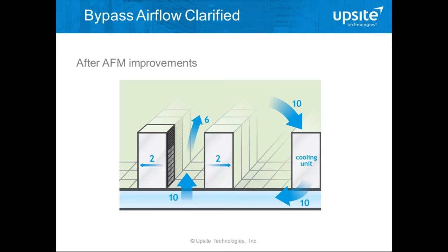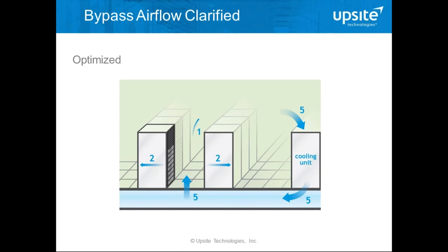Sealing the cable openings is the right thing to do, but it doesn't change the amount of bypass airflow in the room. It directs all the air to the supply tiles — now 10 units comes out of the cold aisle tiles — but the IT equipment still only needs four units total. Six units of air remain unneeded in the aisle and return to the cooling units as bypass airflow. The opportunity is to reduce the amount of air moving through the cooling units and better match supply to demand.